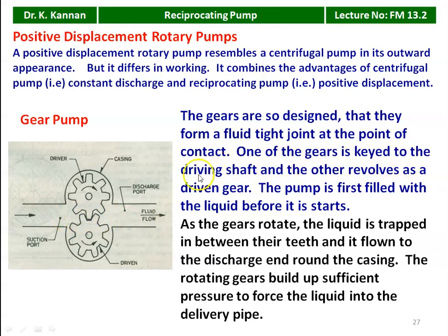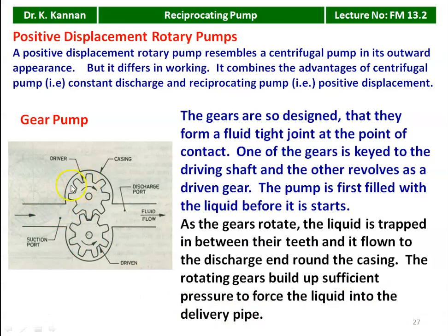One of the gears is keyed to the driving shaft connected to the motor; the other revolves as a driven gear. The pump is first filled with liquid before it starts. As the gears rotate, the liquid is trapped between the teeth and flows to the discharge end around the casing. The liquid is compressed in the gap between the teeth and the casing, and the high-pressure liquid is delivered on the other side. The gear pump is normally used for pumping high-viscosity liquid.